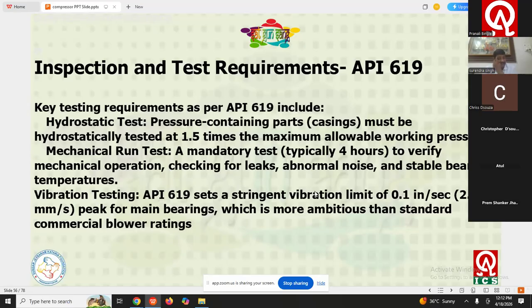And the same check parameters are there. We have to check for leaks, any abnormal noise, and stable bearing temperature. Again, vibration testing is defined in API 619. The vibration limit shall be 2.5 millimeter per second at peak position for the main bearing. How we can check the vibration, we will see in the upcoming slides, where I have shown the instrument picture.